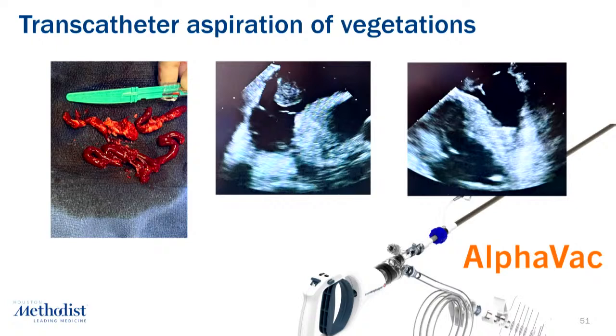This is a case that I did in the cath lab. And again, a very bulky vegetation that would have had significant consequence if it embolized. From the time we got access to removal of the vegetation was less than 15 minutes. And the blood loss, with this device, you don't return any of the blood. So if you go hog wild sucking into the machine, there's some blood loss. But the blood loss was only about 50 or 100 cc's in this case.